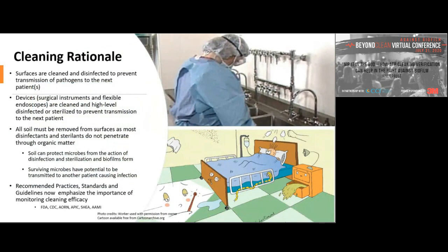The purpose of cleaning is that surfaces need to be cleaned and disinfected to prevent transmission of pathogens to the next patient. For surgical instruments or flexible endoscopes, they need to be cleaned and either disinfected or sterilized. All the soil has to be gone from the surfaces; otherwise the disinfectants or sterilants aren't able to penetrate through the organic matter and can't be efficacious. Soil can protect the microbes — both Joe and Wava talked about how biofilms form and the impact on subsequent processes.